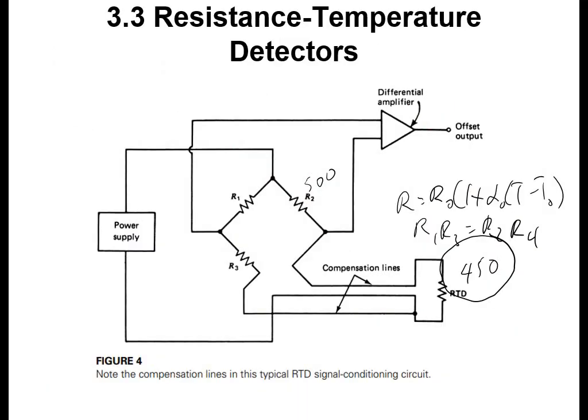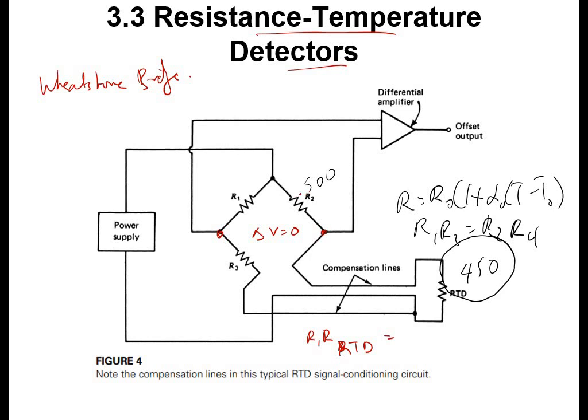This is the part we covered on how resistance changes with temperature and the best fit we can obtain. Now, how to use that in the RTD — we will look at how to use that equation in the RTD. Recalling what we have taken about RTDs: we discussed the Wheatstone bridge. The idea is that if you take delta V, it will be zero based on the resistances. The null voltage equals zero based on: R1 × R_RTD = R2 × R3.